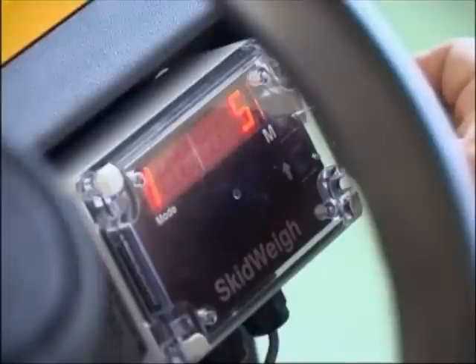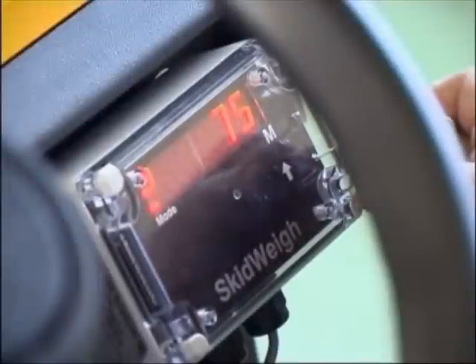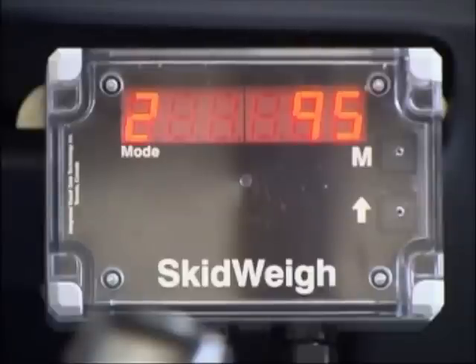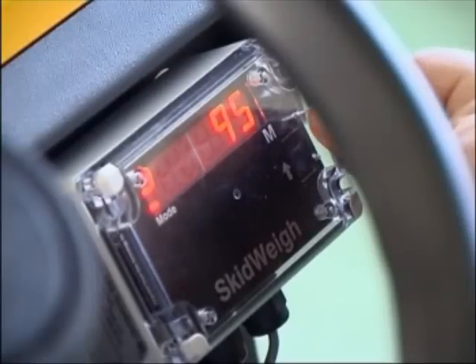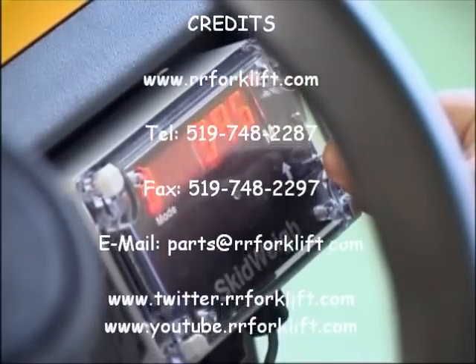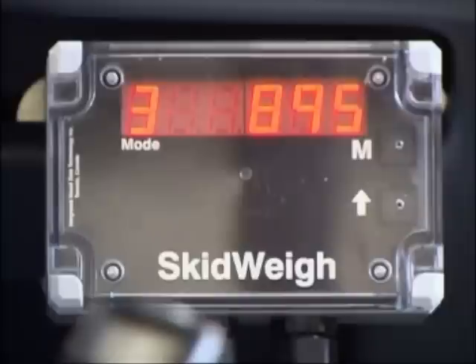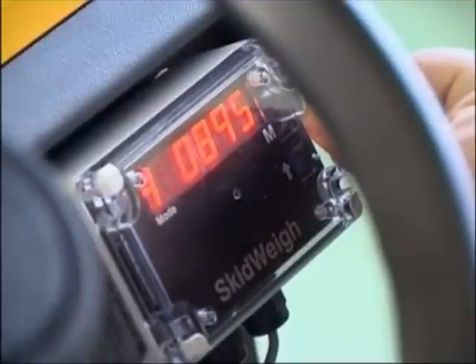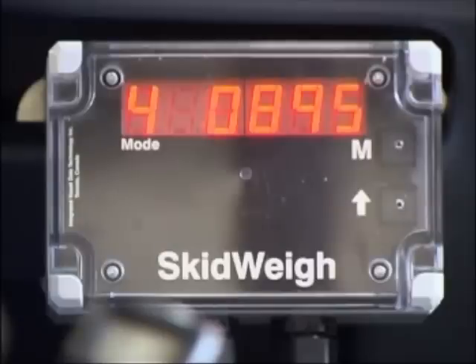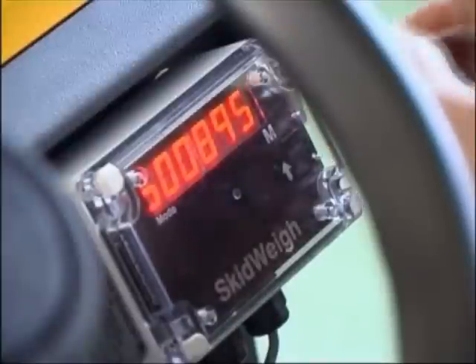Once the number 5 is entered, you must now press the M button to advance to the second digit, in this case number 9. Once the 9 is entered, you must now press the M button to get to the third number, so that we can enter the number 8, which is the first number of the known weight of 895. Again, using the paper clip, press the arrow up button until the number 8 is displayed. Because our known weight of 895 is only 3 digits, the remaining 2 digits must remain at 0. You must ensure that the remaining digits clearly show zeros.